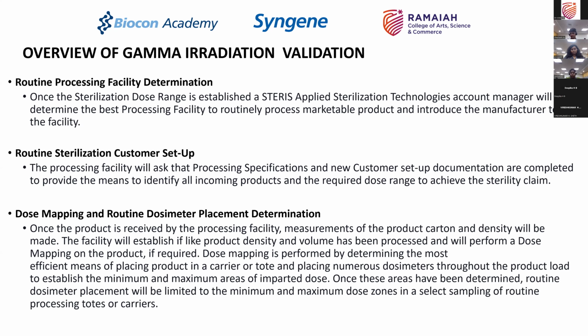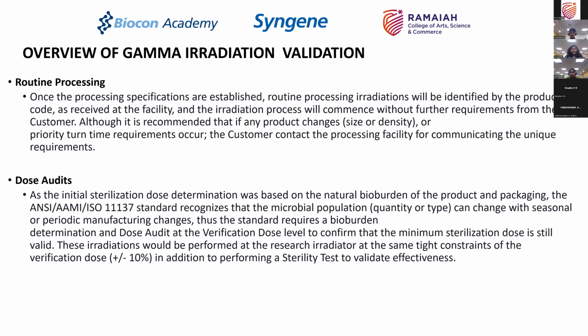So you first design the product, then you design the packaging, then you determine what should be the volume, then you determine the dose rates based on theoretical data. Then you conducted a small irradiator study. You fixed the range. You then decided to give this to the right kind of a facility. Now you did the documentation which was required. Now you are doing the mapping. So this is the process of validation which is happening.